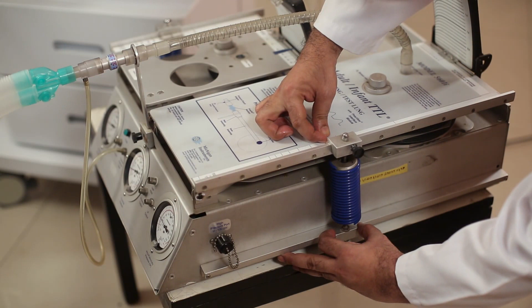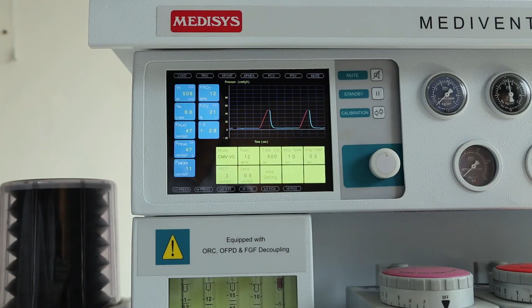The machine has several safety devices. One of them is breath-to-breath correction. What we mean by that is that if the compliance of the patient goes down for some reason, the machine will automatically try to correct it and bring back the normal tidal volume we have set. And this is a great blessing in patients who may develop pulmonary edema, who may develop bronchospasm during anesthesia. There is a compliance calibration.